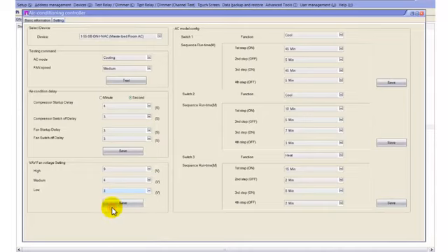So usually we use 30%, 60%, 90% or 100%, which means 10 volt. This is based on your CFM calculations of the rooms, the size of the rooms, and the AC, because the VAV is normally used to split the airflow into separate rooms or separate areas. Mainly we use it for offices. So in case you have a VAV, you can select the voltage of the opening of the shutters based on the CFM and the airflow. This is just the airflow control.